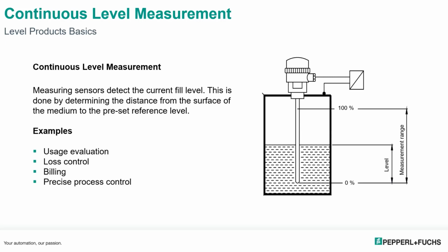Continuous level measurement means that we detect the current fill level. So wherever the level is, we can give a 0 to 100% reading of wherever it is in the tank. Usually this is a 4 to 20 milliamp output, but we also have some Profibus and fieldbus, and a lot of these units with the 4 to 20 milliamp are HART compatible. Examples of usages are evaluating where the levels are in the tank.